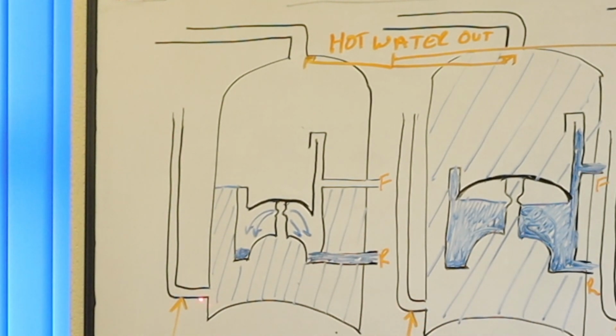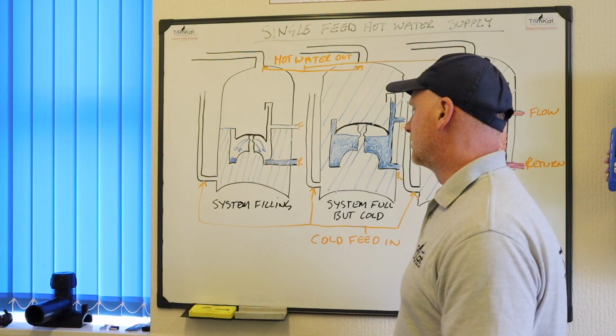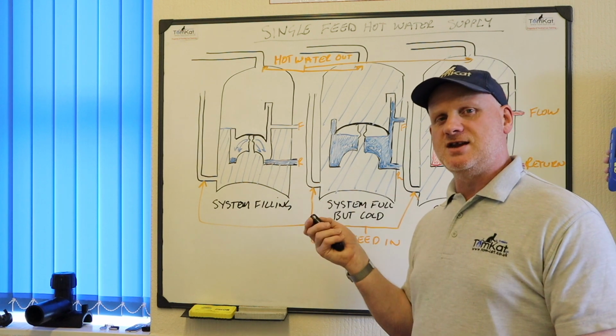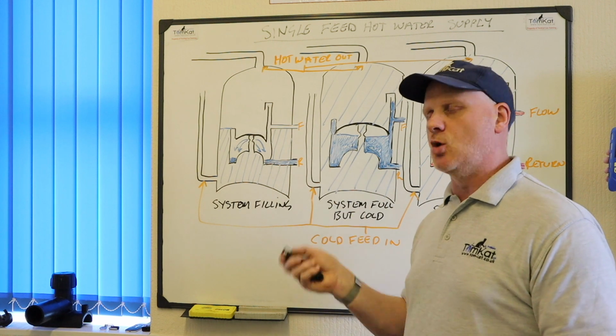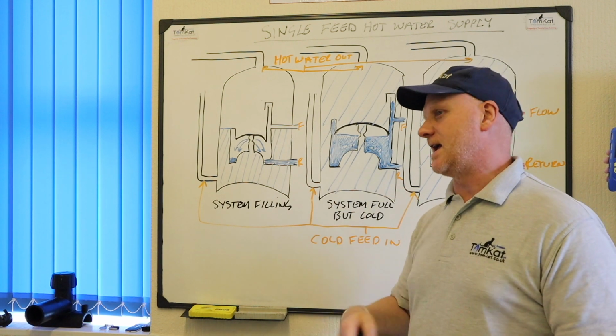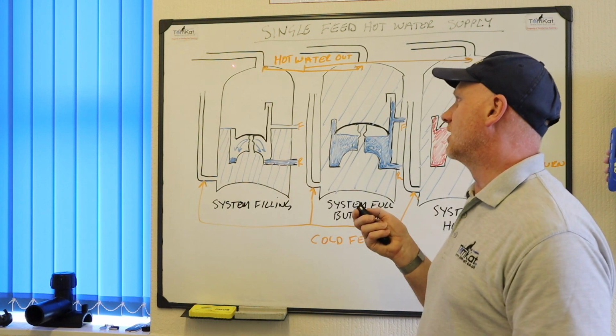So this is our cold feed coming in. So this is coming from the feed system. Now the water inside the cylinder is cold, and what it's doing is it's filling the heating system through the primary return, because it can't get through the flow yet, because it fills through this special bubble. So what happens is there's 2 bubbles here. There's one at the top here and one at the bottom here. So while it's cold, the water comes in, goes up there through the gap. The gap's normally at the top there and flows over the top and then down into the heating system and completely fills the radiators. So when you're initially filling and draining these cylinders, you should always have the hot tap open, because the furthest away hot tap downstairs will get rid of all the air through the top here.